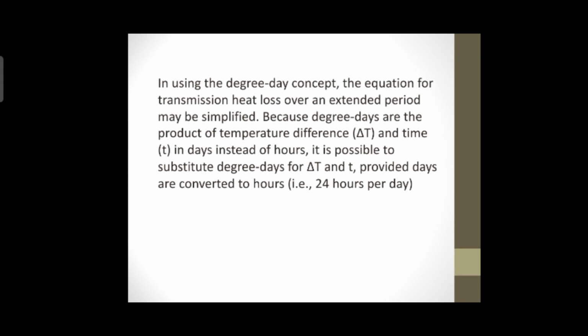Monthly and seasonal calculation. In using the degree day concept, the equation for transmission heat loss over an extended period may be simplified because degree days are the product of temperature difference or delta T and time in days instead of hours. It is possible to substitute degree days for delta T and T, provided days are converted to hours.